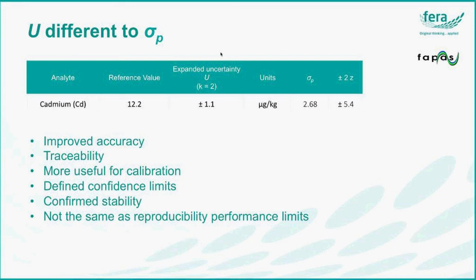They are different statistics. The uncertainty gives you improved accuracy, traceability, it's more useful for calibration, it's a defined confidence limit, and we also provide the datasheet with a confirmed stability. We provide that based on formal stability experiments, and it's not the same as the reproducibility performance limits.